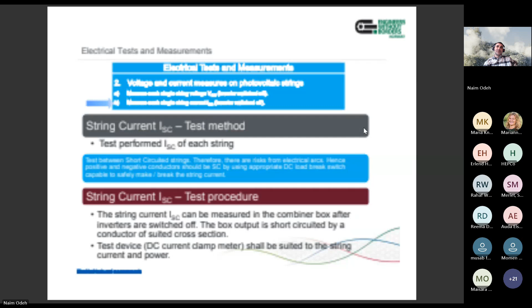The third test is the short circuit current (Isc). It's the same as for the string VOC test. You first follow the same procedure as discussed for VOC: check the connections for the string. If all connections are okay, MC4 connectors are okay, and modules are connected properly, then you short the string plus with minus and use a clamp meter to check the current in the string.